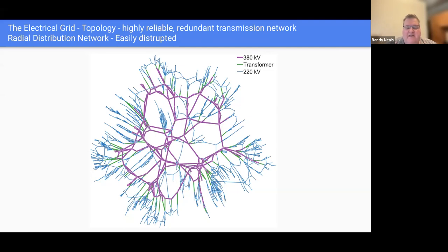But the edges of our network, those blue lines running up and down our streets, are actually a series of radial lines going outward, many without redundancy. The core of our electricity system, the high tension transmission lines on the big steel towers, tend to be organized in rings with redundancy, while the wires running down our streets tend to lack that redundancy.